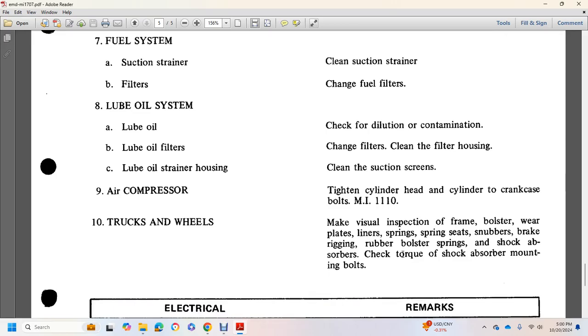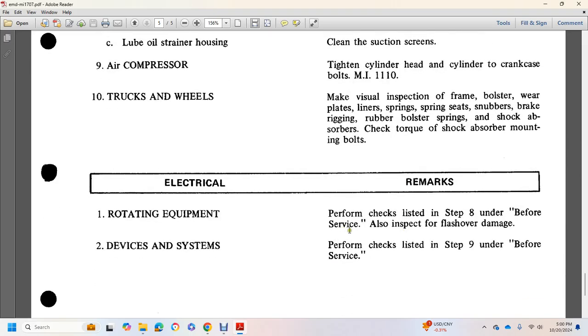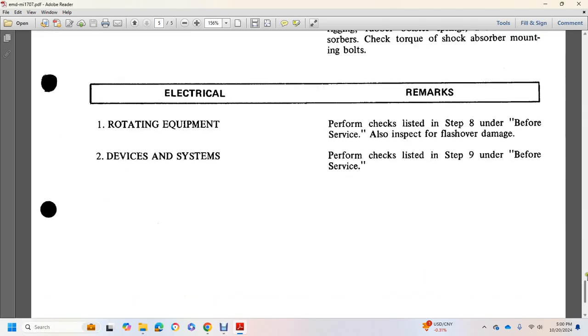Truck wheels, make visual inspection, frame, bolster, wear plate, liner, spring seats, brake rigging, rubber bolster, spring, shock absorber. Check torque for the shock absorber mounting bolts. Electrical system, rotating equipment, perform checklist step 8 under before service, also inspect for flashover damage. Device system, perform checks listed, step 8, 9, under perform services.